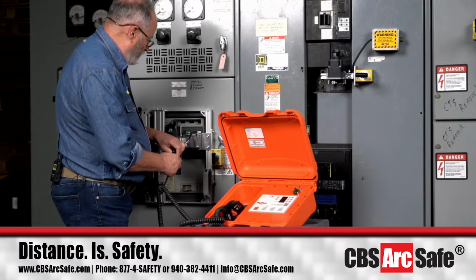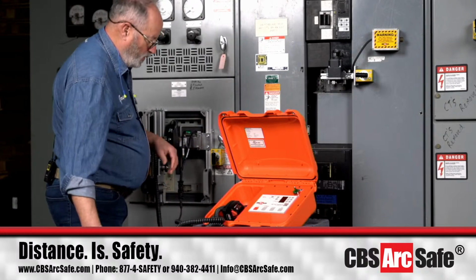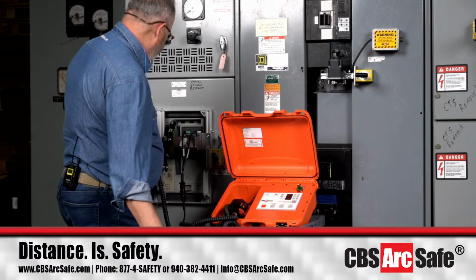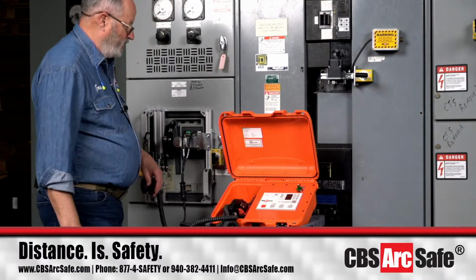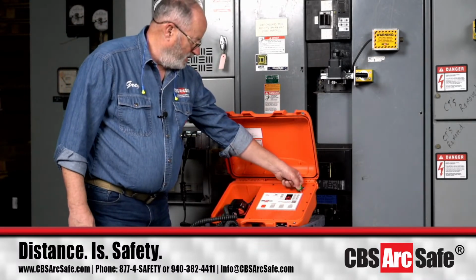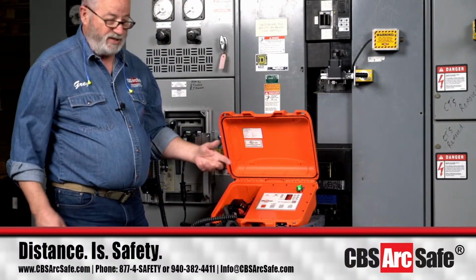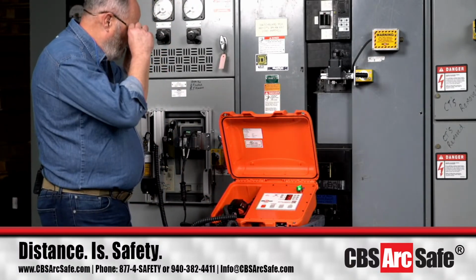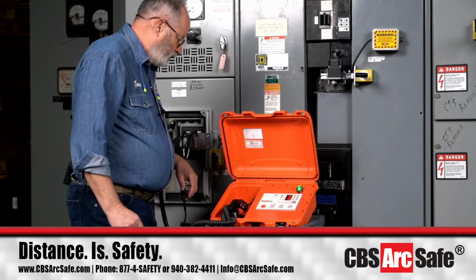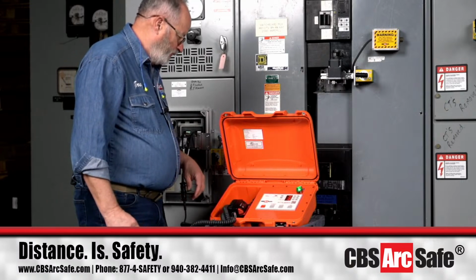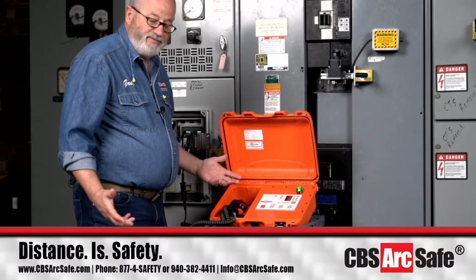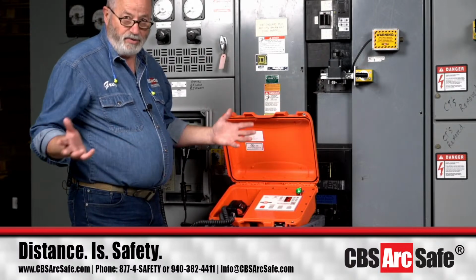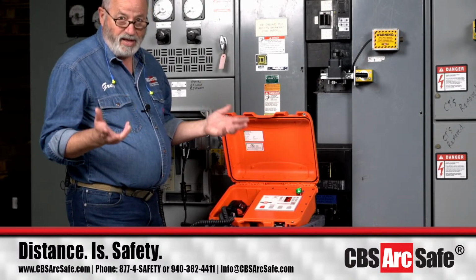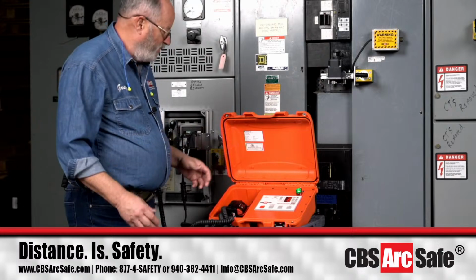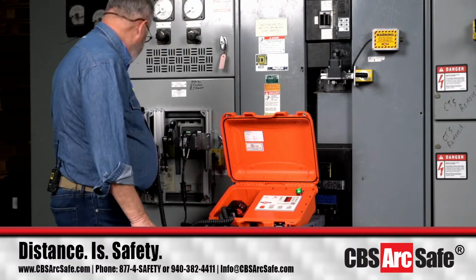So the electricians who were wiring the place had actually asked the contractor if they could have an arc flash study done, and they were the ones that pointed out the high incident energy levels. When you're dealing with 5,000 type amp breakers, you've got a limited grounding field, you're always going to have high incident energy numbers driven by that. So let's take a look here.